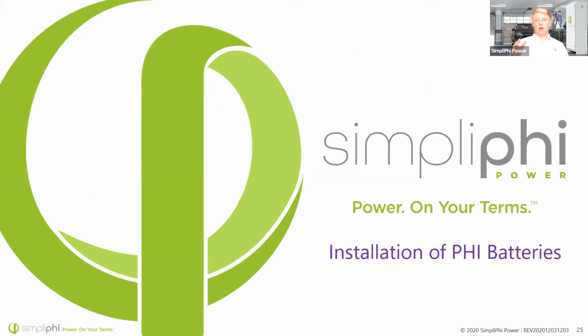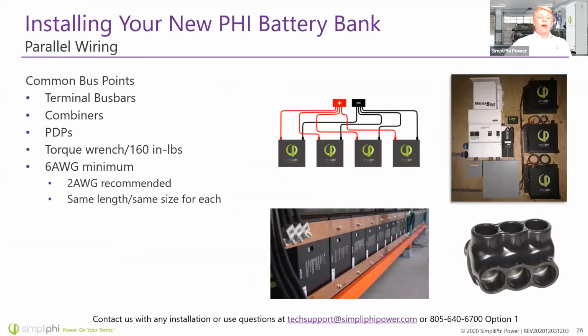So now let's talk about the fun part, installing your Phi batteries. I love that we have a simple, understandable wiring method that we require. So ultimately, each positive terminal needs to be routed directly to a positive common bus bar, and the same with all the negative terminals to a negative common bus bar, or connection point in general. It doesn't need to be a bus bar necessarily. Now, using the same size, same length cable for each connection here is essential. This is going to promote balancing of the battery, make sure each of the batteries are at the same state of charge.